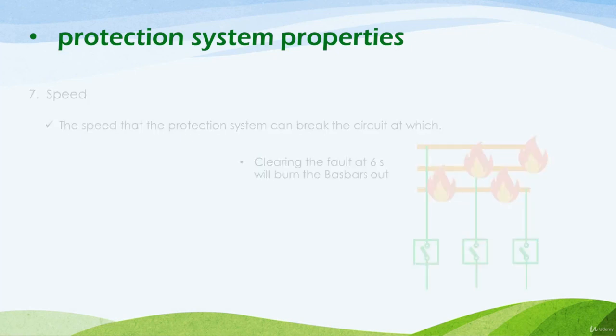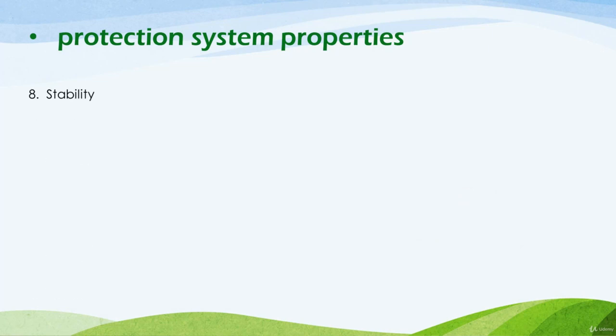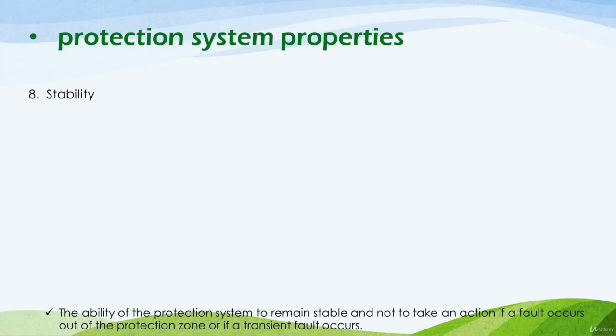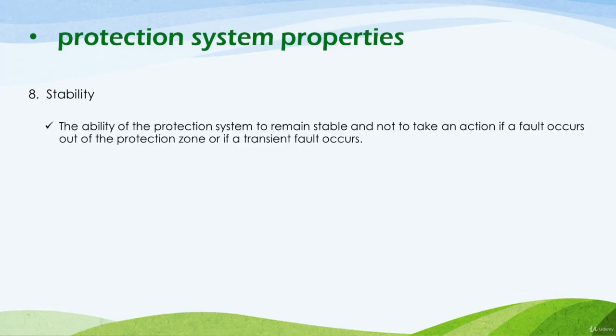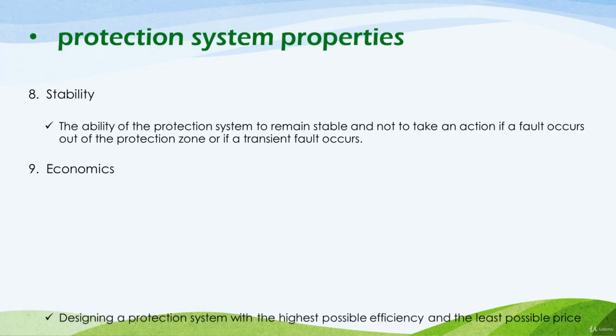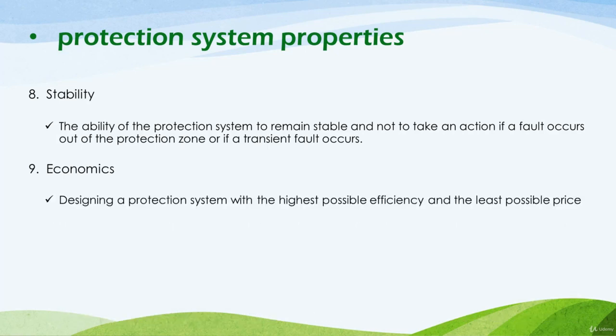Very good. Also, the eighth property of the protection system is its stability, which is the ability of the protection system to take action only if a fault current occurs in its zone. We need the protection system to act only when a fault current occurs through its zone, to have a stable protection system. And the ninth property of the protection system is related to economics, as we need the protection system to be as efficient as possible, and at the same time to cost us as little money as possible, or to have the least possible price. So that's for the economics.